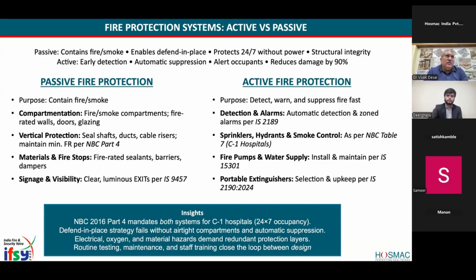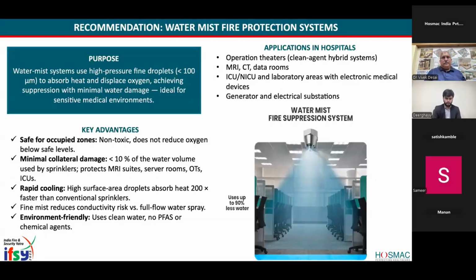You must have read about Hong Kong, one of the more developed cities, where there were 120 deaths in a residential housing area because it was not maintained properly. Those are things we have to be extremely careful about, especially if you are going for high rise buildings, which is what hospitals are probably trying to do. There is one more system which has come of late, and some hospitals in Gujarat have tried it out. It is called a water mist fire protection system. Because of the fine droplets, they are able to absorb the heat and thereby displace oxygen, achieving suppression with minimum water damage.